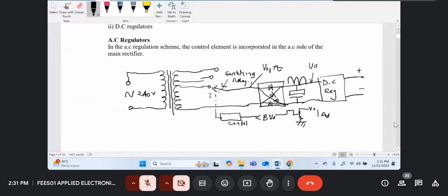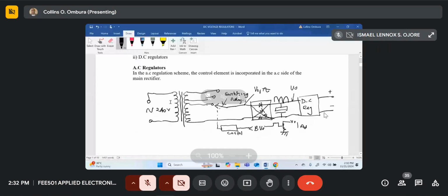So in AC regulation, this control changes the taps of the transformer secondary depending on the output voltage, to control it to the prescribed value. That's what I mean by the control element being incorporated on the AC side of the mains rectifier. This is sometimes called a voltage stabilizer, used for things like fridges—not the small electronic type. This one normally incorporates a transformer, so it's bulky and heavy.